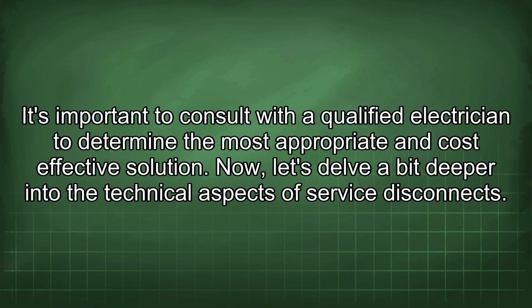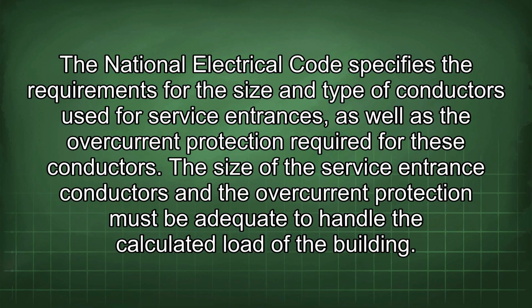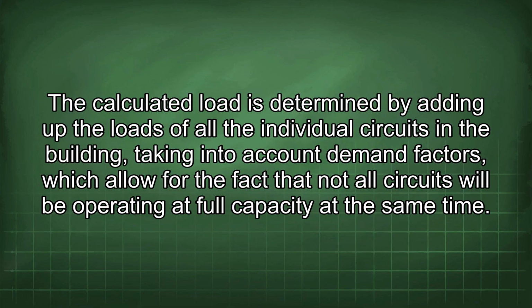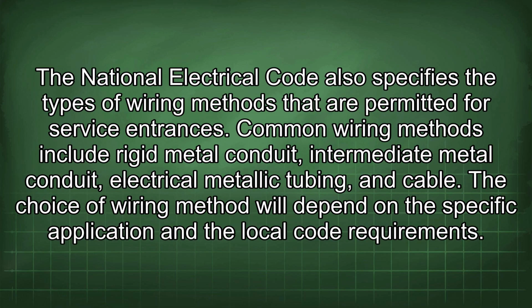Now let's delve a bit deeper into the technical aspects of service disconnects. The National Electrical Code specifies the requirements for the size and type of conductors used for service entrances, as well as the overcurrent protection required for these conductors. The size of the service entrance conductors and the overcurrent protection must be adequate to handle the calculated load of the building. The calculated load is determined by adding up the loads of all the individual circuits in the building, taking into account demand factors, which allow for the fact that not all circuits will be operating at full capacity at the same time.